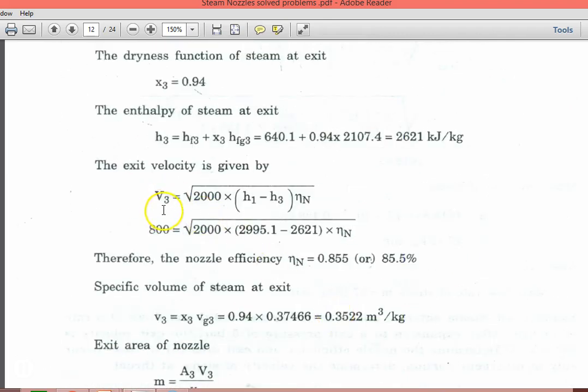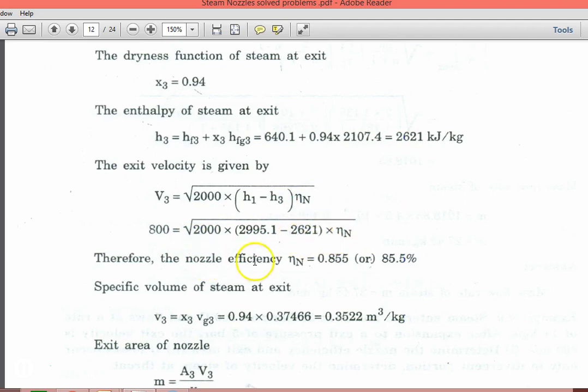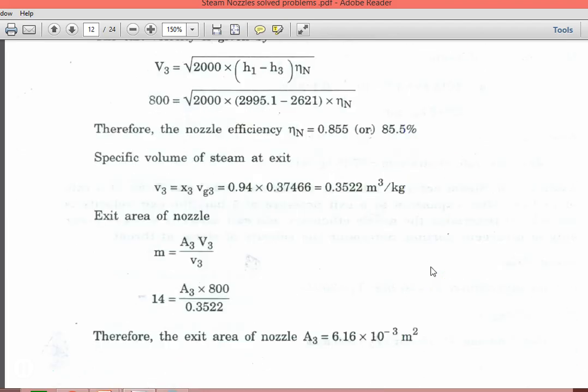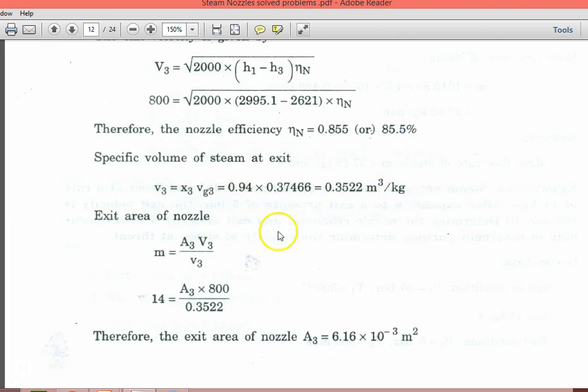The velocity at the outlet is given as 800 meters per second, equal to square root of [2000 into (H1 minus H3) into nozzle efficiency]. Substituting and calculating, nozzle efficiency is 0.855 or 85.5%. The specific volume of steam at exit: V3 equal to X3 into Vg3 equal to 0.3522 m³ per kg.